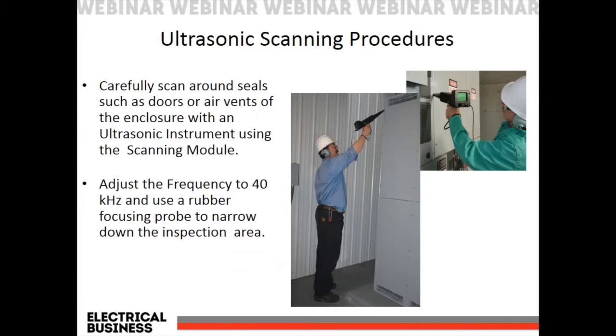All right. So, how do we take our equipment now? We know what the sounds are, but how do we do the scan? Here's an example where we're doing airborne testing, where we would scan around the seams or even the top or the air vents of an electrical panel, an asset, and scan around those seals or door and air vents of the enclosure, because high frequency sound will not penetrate through solid objects, but when we have a path of least resistance, like the seals or the air vents, it will escape through that, and we can easily point out that there's a sound in there. We would use a 40 kilohertz frequency based on ISO standards as well to focus and narrow down the inspection area. All right.